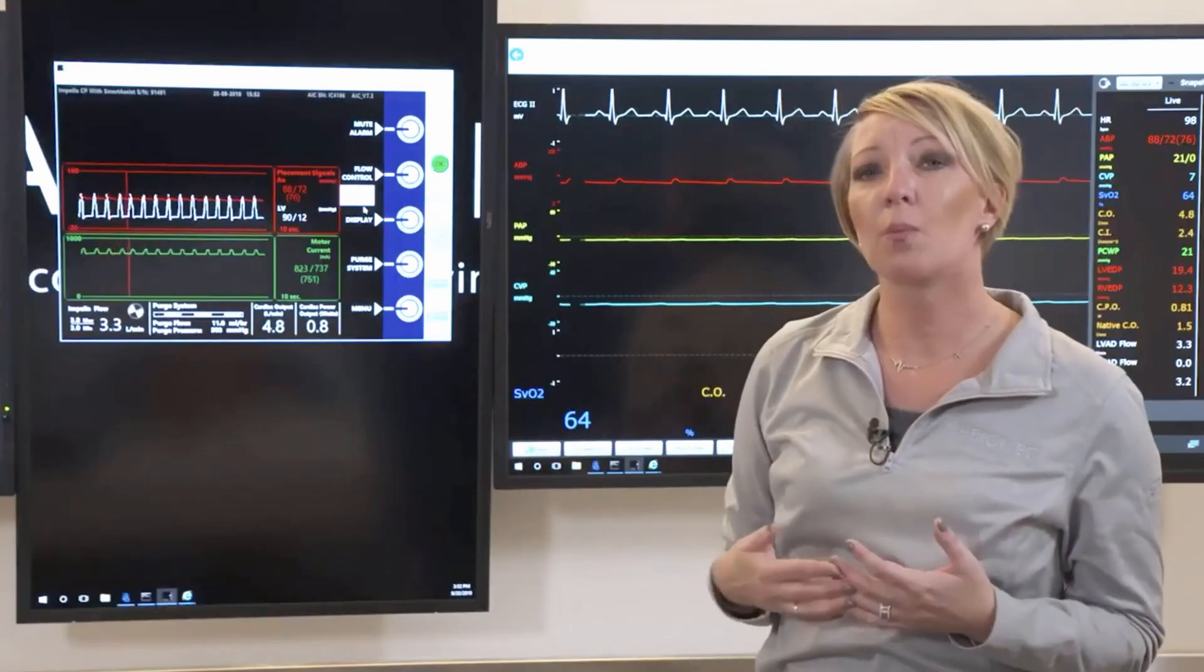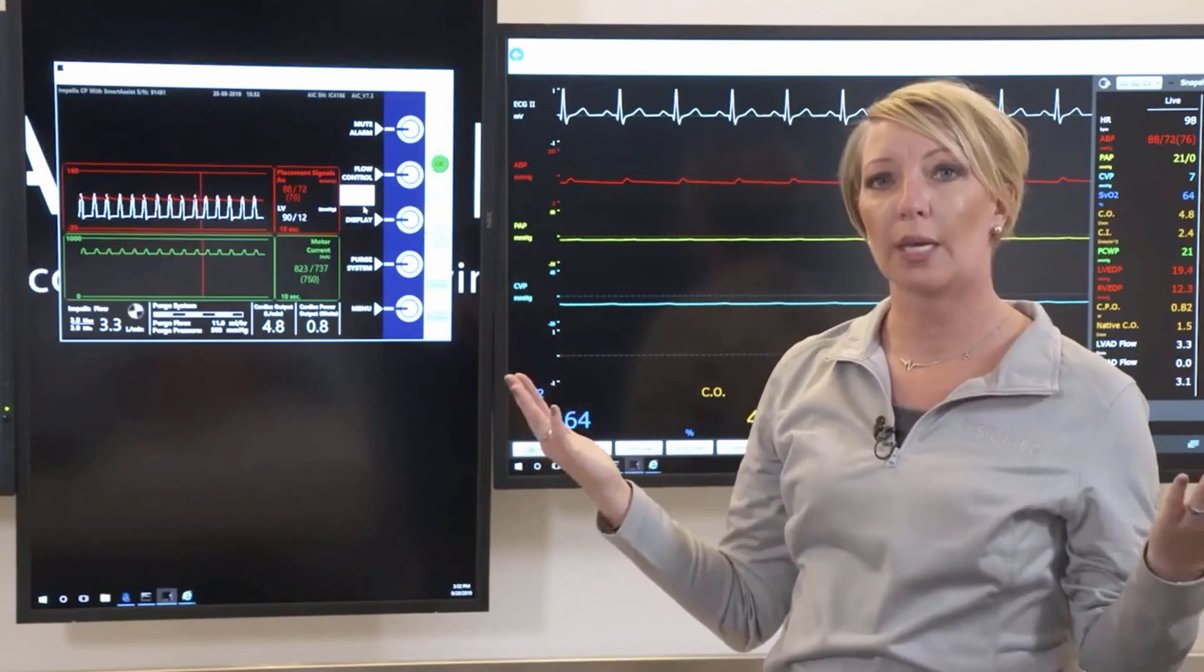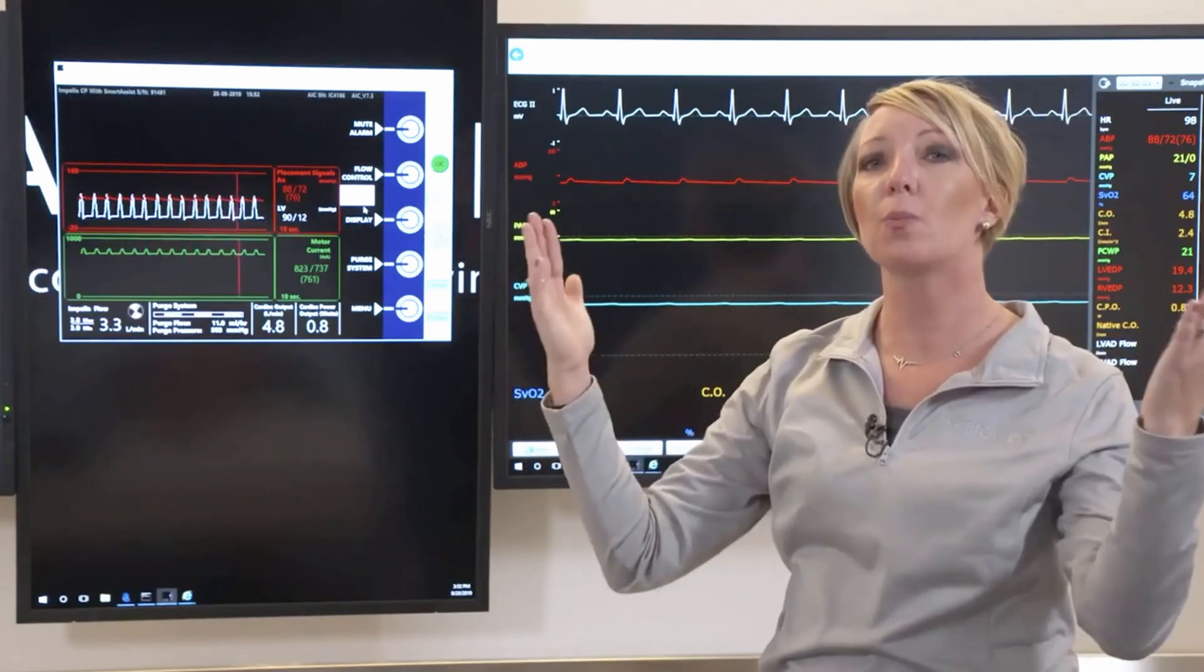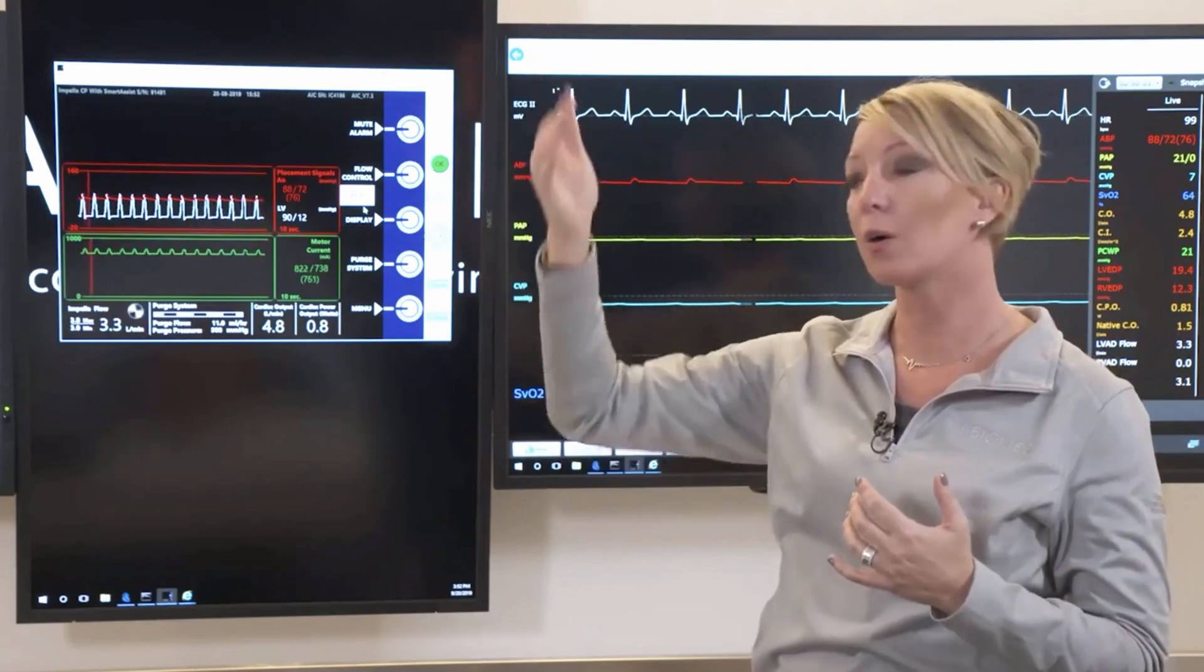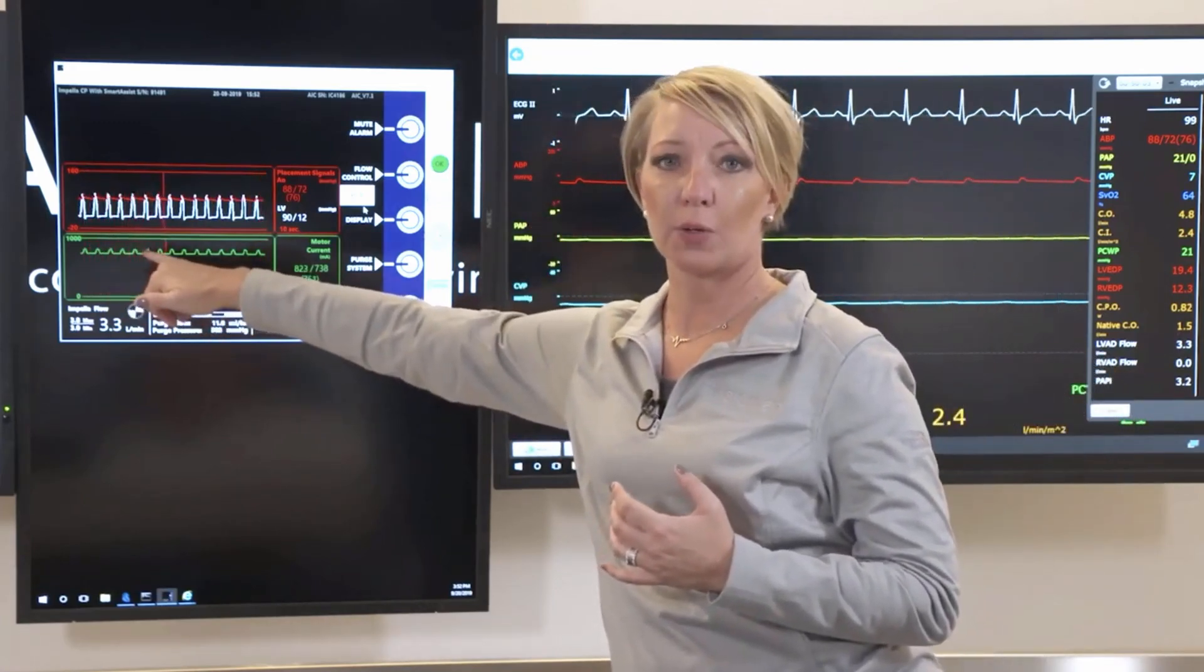So what is motor current? Motor current is essentially looking at the amount of energy and flow through the cannula. When the valve is open, I have more energy, more flow, which will be reflective of the peak on our motor current.